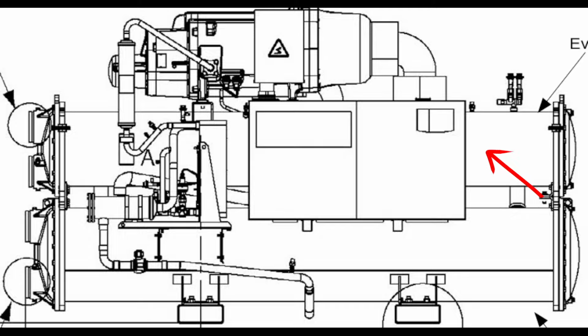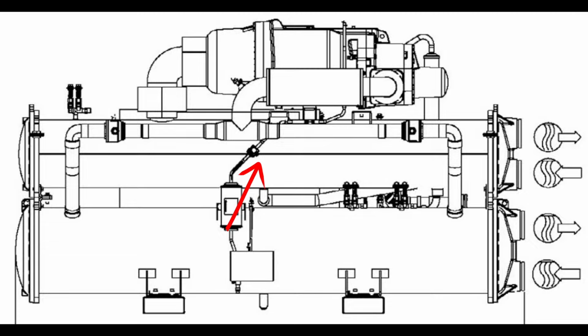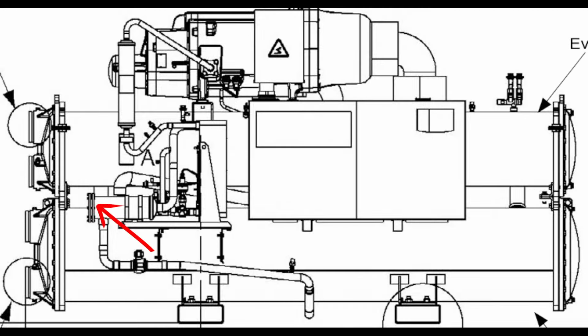Okay, suction line comes off of the evaporator. This would be a discharge line here and here. And if we come over here, we can see that on this side, we come off, we have a muffler into a T, or call it a header, doesn't matter. We have an isolation valve. They're just ball valves, and that feeds into our condenser. So we know immediately evaporator, condenser. Now, if we were to walk up to this machine, we would likely see that this top one is insulated, the bottom one is likely not. That would also be another obvious giveaway, but just from a schematic alone, we can determine which is which, just based off of our piping.